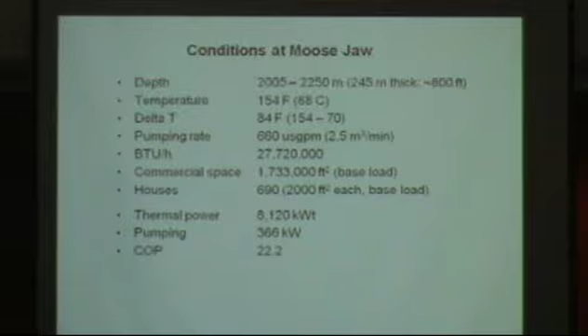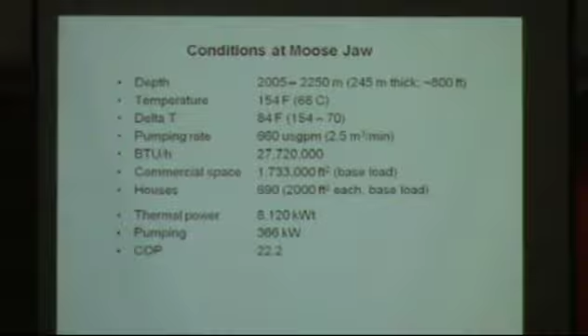To put the energy in a different perspective, it's equivalent to generating about 8,100 thermal kilowatts. Now, it takes electricity to pump all this water around—that's really all we're doing is circulating water. An estimate of about 366 kilowatts would be required to pump all the water. So the ratio between the thermal power generated and the power consumed, our COP, or coefficient of performance, is about 22. That's a significant return on energy in versus energy out.